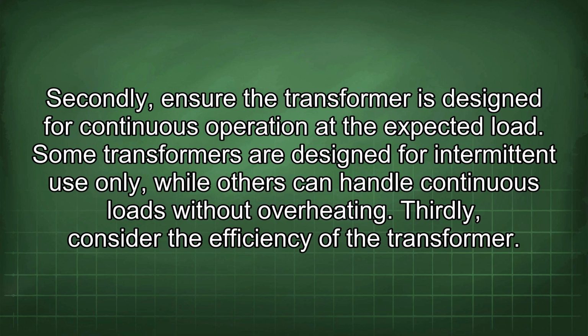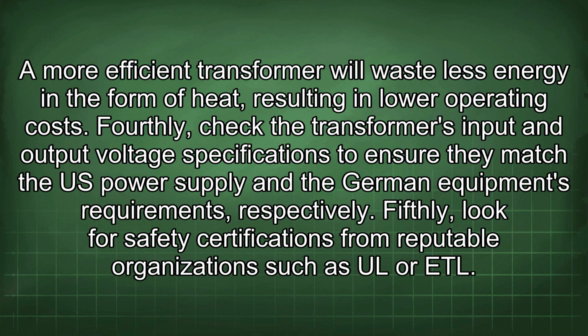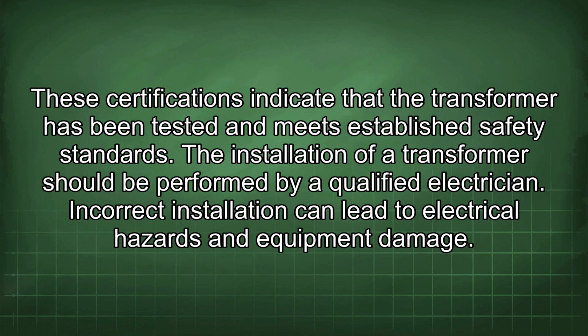Thirdly, consider the efficiency of the transformer. A more efficient transformer will waste less energy in the form of heat, resulting in lower operating costs. Fourthly, check the transformer's input and output voltage specifications to ensure they match the US power supply and the German equipment's requirements, respectively. Fifthly, look for safety certifications from reputable organizations such as UL or ETL. These certifications indicate that the transformer has been tested and meets established safety standards.